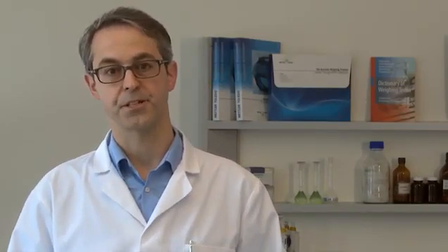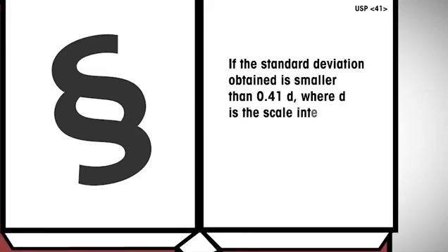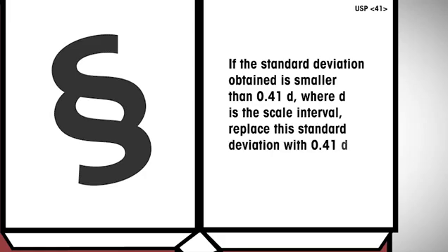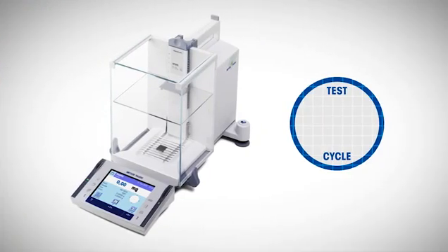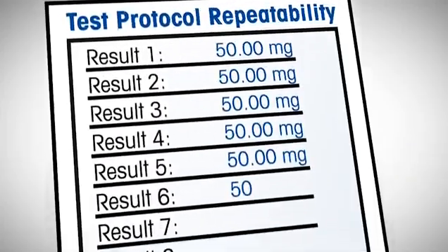This change was pretty straightforward. Here comes something new, a lower limit for the repeatability test. If the standard deviation obtained is smaller than 0.41d, where d is the scale interval, replace this standard deviation with 0.41d. So in case the standard deviation is 0, or just very small, the readability of the balance is not high enough to detect deviations.